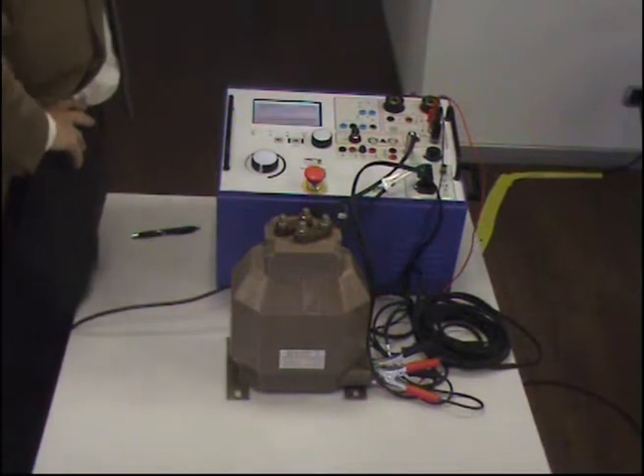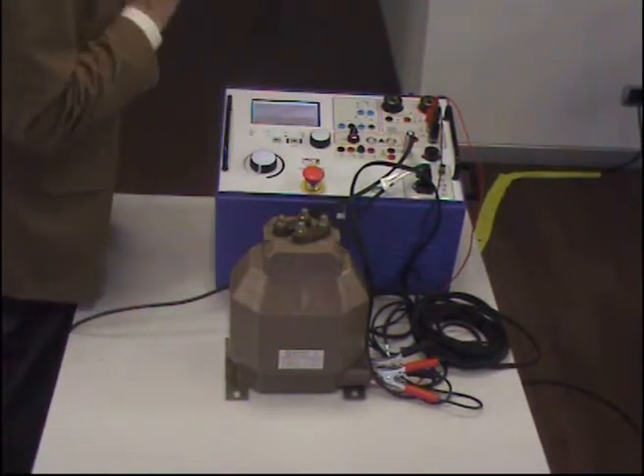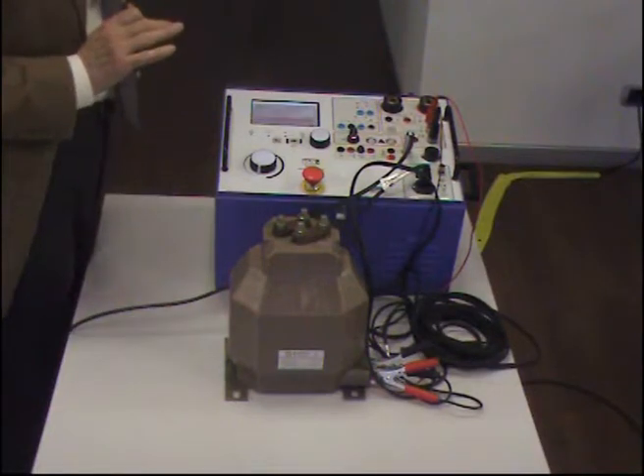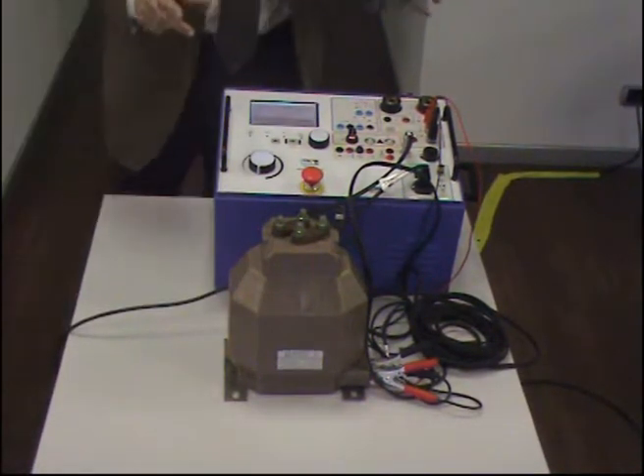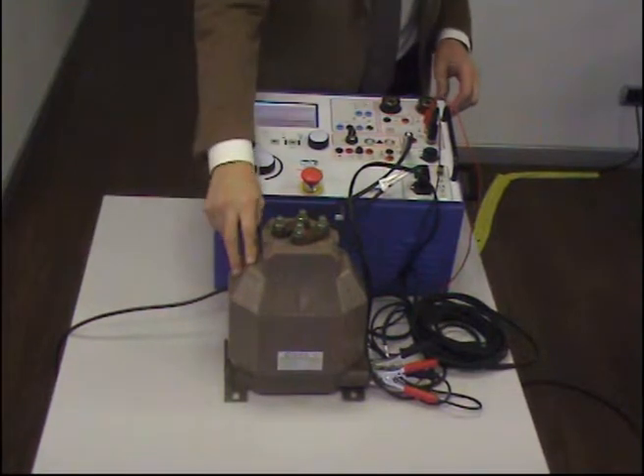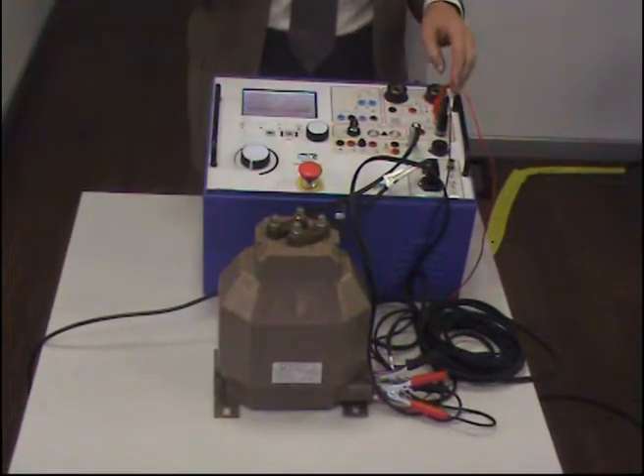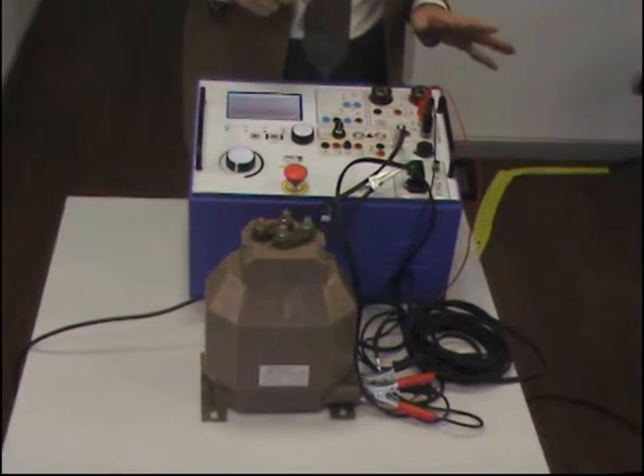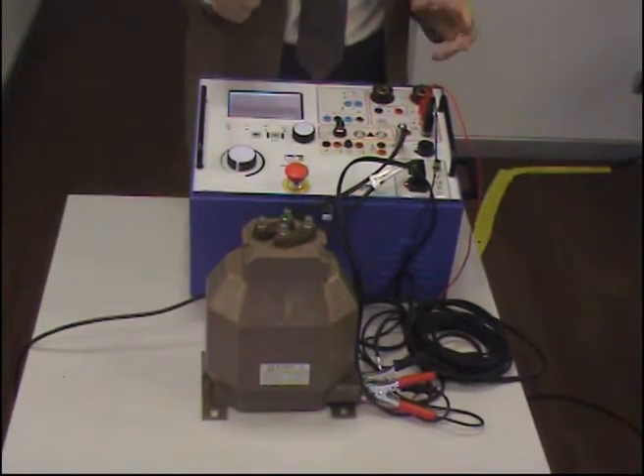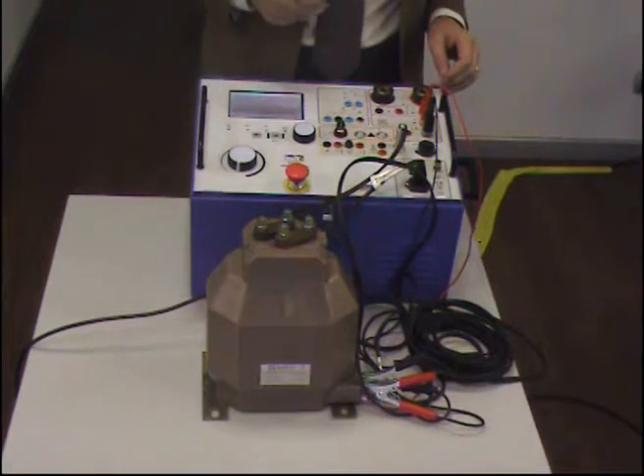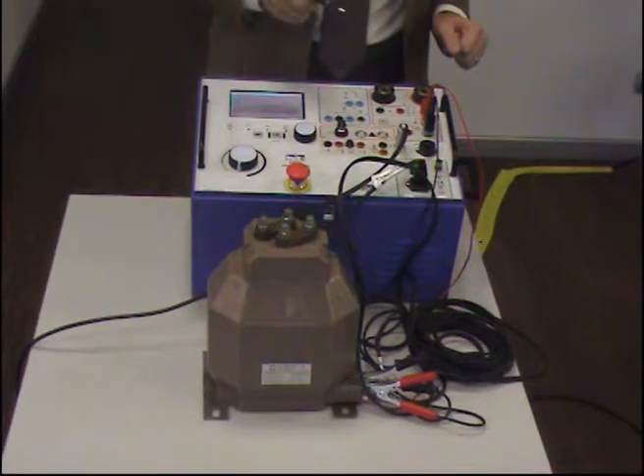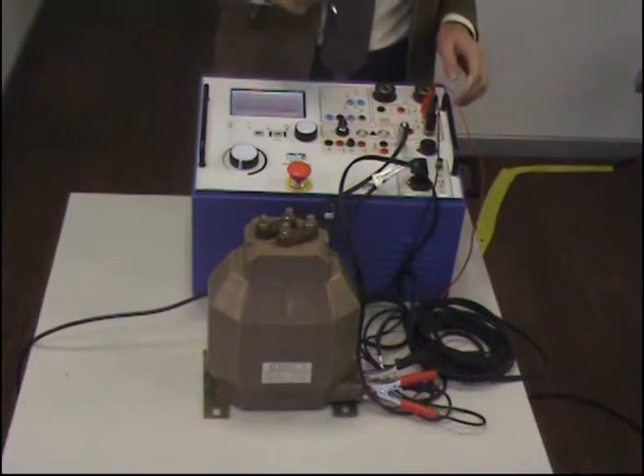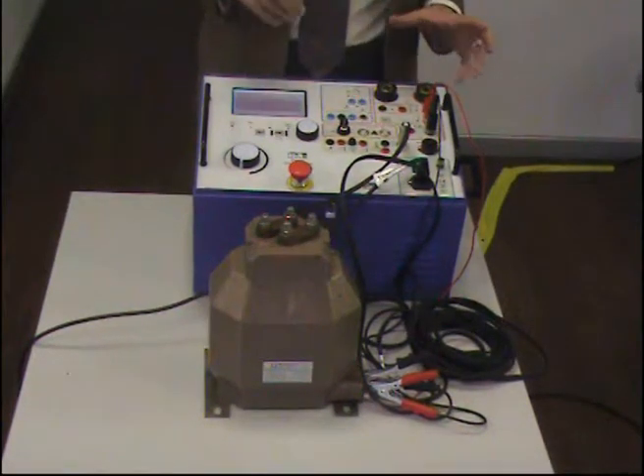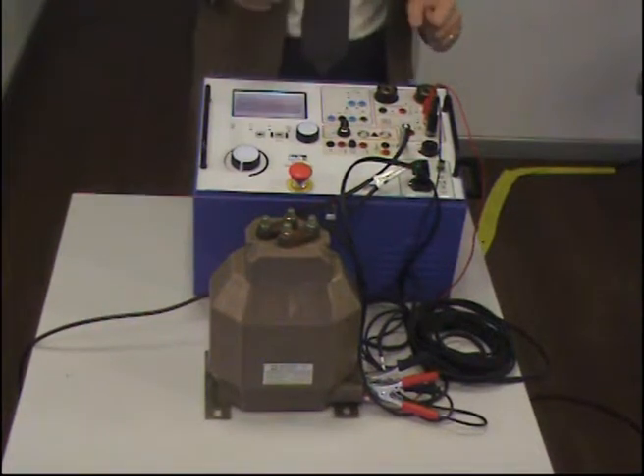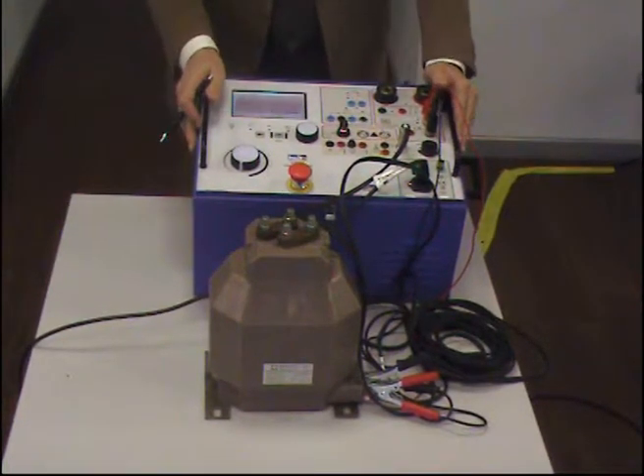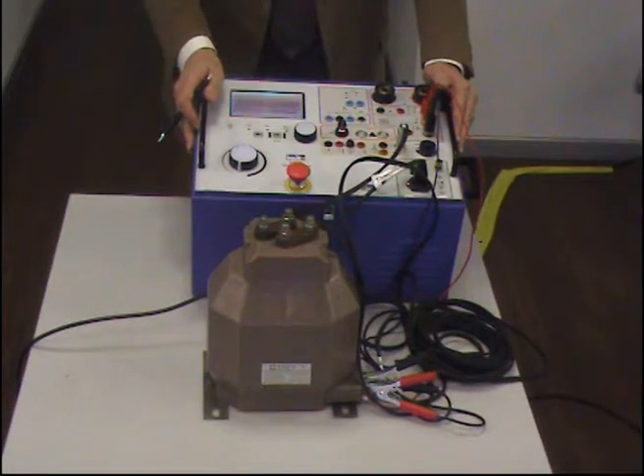Now, next test is winding or burden resistance. What I want to do is to measure the resistance of this secondary side of the current transformer. The winding of the secondary side has some turns, so the resistance is not negligible. The point about measuring the resistance is that there is a problem of danger, and if you are to measure the resistance of a big transformer, this danger can be high.